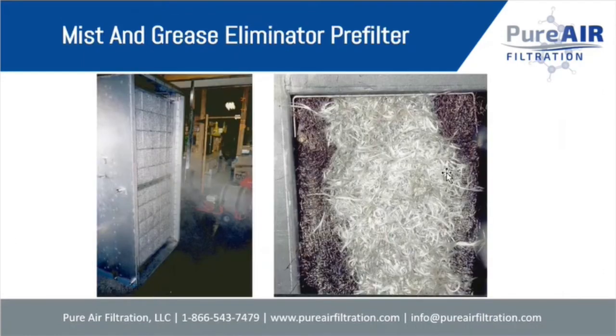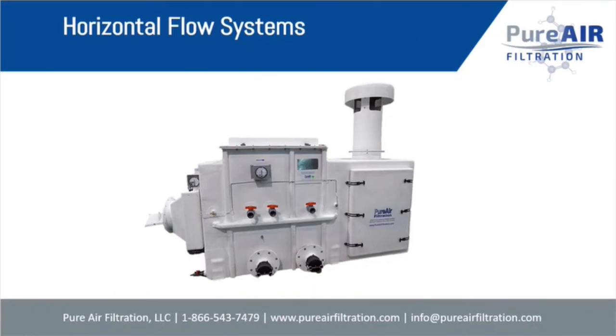So is that what you use if you're trying to handle multiple gases? Yeah, almost all of our systems. We very seldom have a customer that says, I only have one gas that needs to be removed. He may say this is the primary gas, but we also have these other things. And certainly, without a doubt, wastewater odor control is one of those applications. So here, we would put a bed of our H2S catalyst adsorbent, called Sulfazorb XL, the one that's 66% capacity. And afterwards, we would often put that blended media to capture mercaptans and other odors. Very effective. Typically a 2/3, 1/3 ratio.